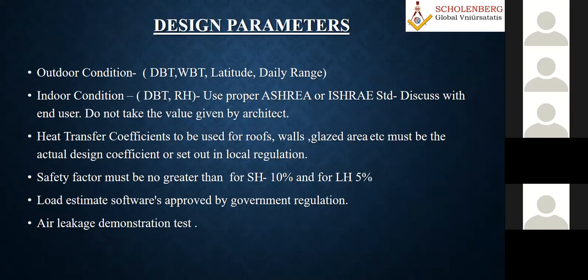Similarly, when you take the outdoor condition, you have to always consider latitude and daily range. This is something many times people don't consider. Maybe in your software it may be there. Similarly, when you go for the indoor condition, you can always try to have flexibility on what the end user wants. Normally the architect may not give the data, as I told you; in every air conditioning job, the initial design input is always raw data. You don't get even 10% of the data you want, and many times you have to make assumptions. So data collection is also an art rather than a science.